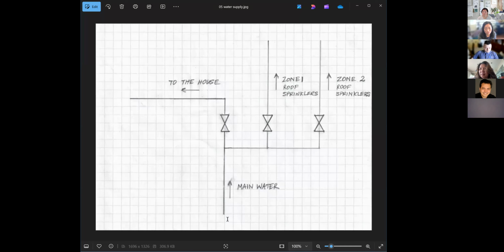Here is the diagram of the connection. Main water comes to the house. Before the main water gets to the shut-off valve of the house, I tee off and route it to zone 1 and zone 2 of the fire sprinklers on the roof. In a normal situation, these 2 valves are closed, this one is open, and the main water goes to the house.